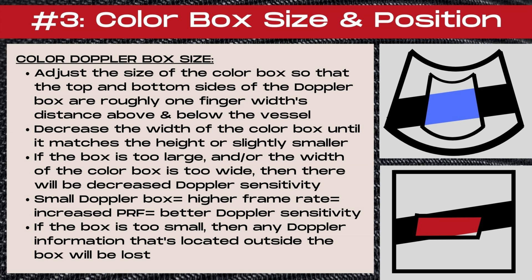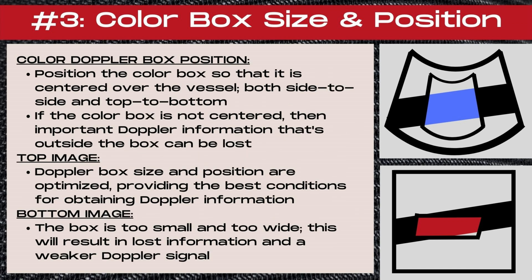A small Doppler box equals a higher frame rate, which means an increased PRF, which leads to better Doppler sensitivity. If the color Doppler box is too small, any information located outside the Doppler box will be lost. Position the color Doppler box so that it is centered over the vessel, both side to side and top to bottom. In the top image, the Doppler box size and position are optimized, providing the best conditions for obtaining Doppler information. In the bottom image, the box is too small and too wide, resulting in lost information and a weaker Doppler signal.